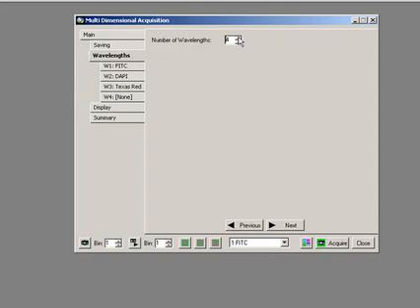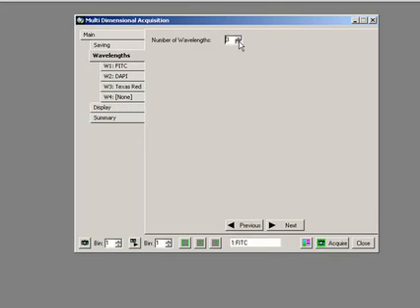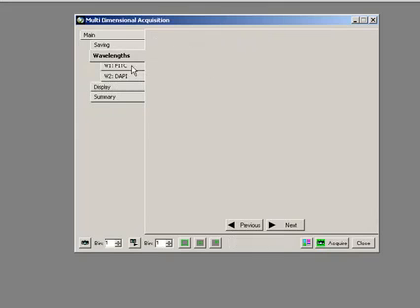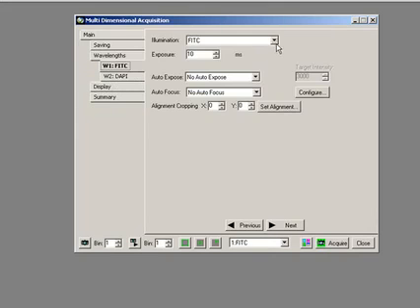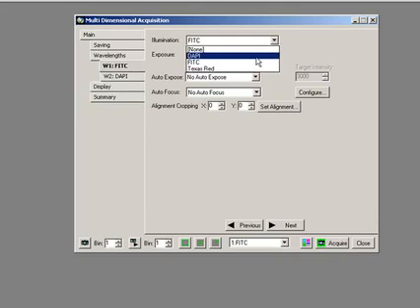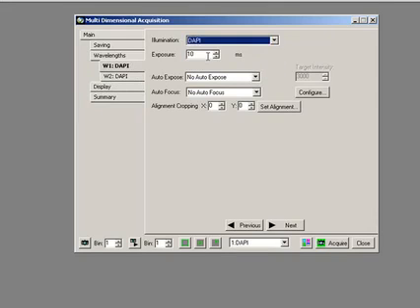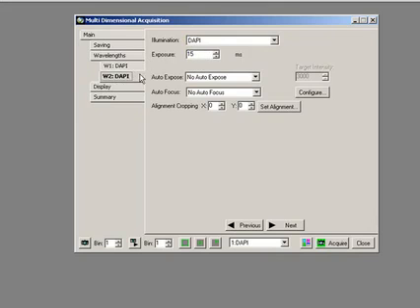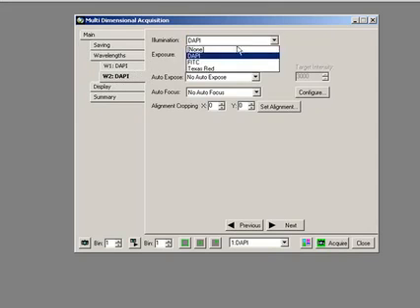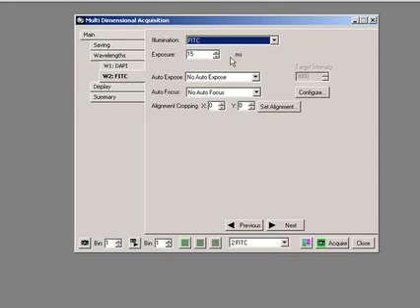So I can say in here, and I can keep on growing. So I've got like five wavelengths here, but in reality, let's just do two channels. So I pick my first one, and I say, you're going to be DAPI, and you're going to have an exposure time of five milliseconds, and I'm going to pick my second one and say, you're going to be FITC, and you're going to have an exposure time of 15 milliseconds.